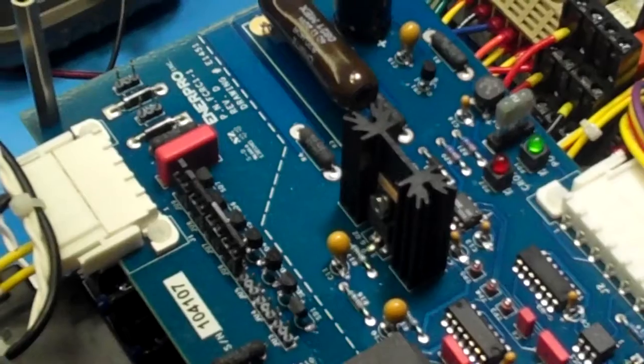It's not crowbar because we have 24 volt AC and because we are below the 650 threshold. Also on the second board, we can know that the unit is crowbar ready. It's ready to crowbar. We haven't built up any voltage, so we have another LED in the back that indicates high voltage, and yet another LED in the middle that says the unit has crowbarred.